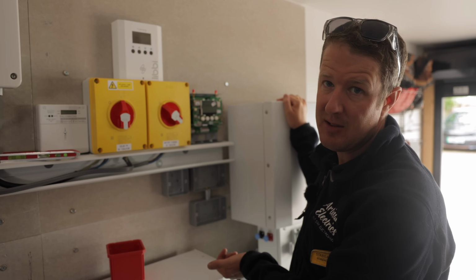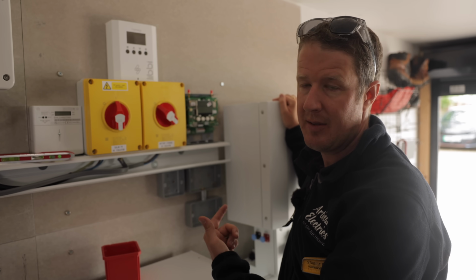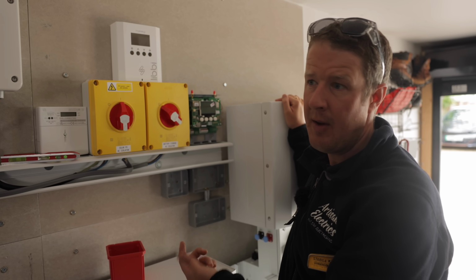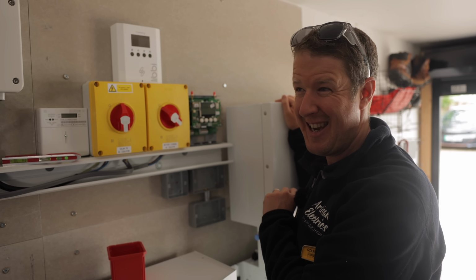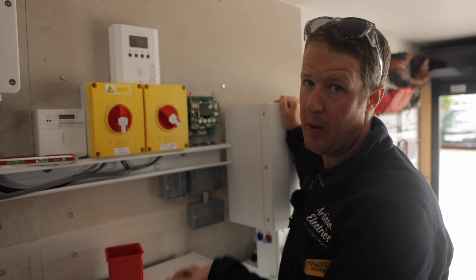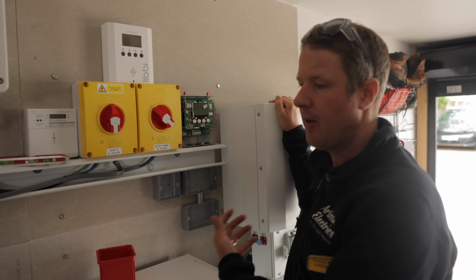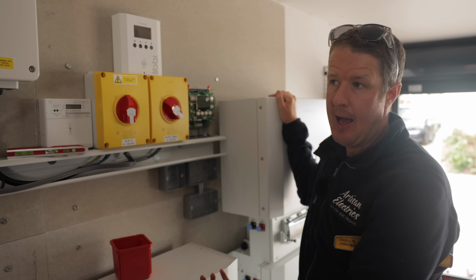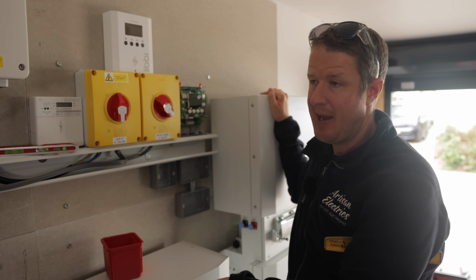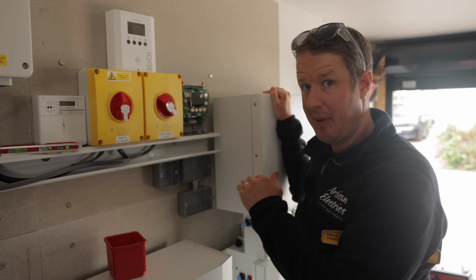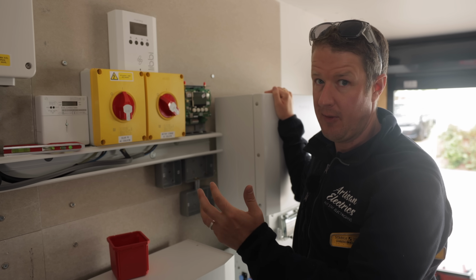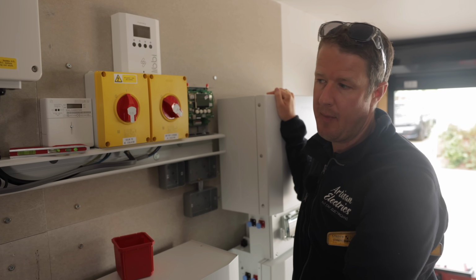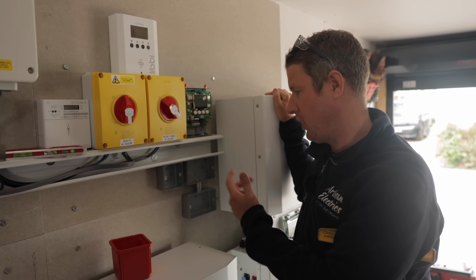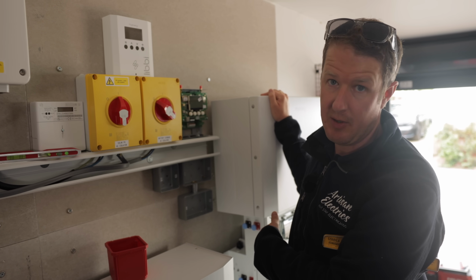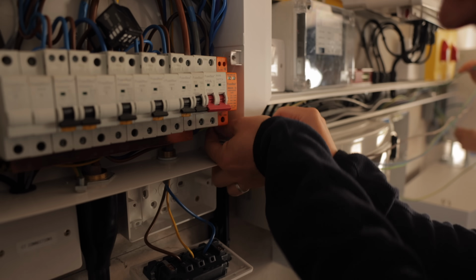Now it is EPS, not UPS, which means that it does skip a cycle or a half cycle in the sine wave, so it's not necessarily going to be instantaneous, but is pretty quick, to be honest. So it's good for backup power in an emergency, but if you need UPS, which is completely uninterrupted power supply, like for very essential computer equipment and stuff like that, you shouldn't necessarily be using the backup side of the Libbi for that.